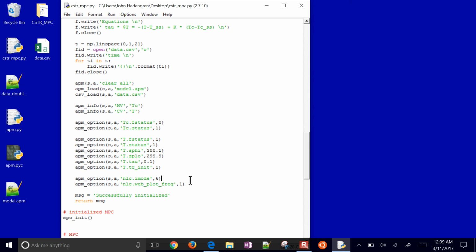I'm going to change this to 0. I'm just going to put a pure deadband there. That's often the easiest one to do. And then in that case, I don't need the tau value, because it's just going to say try to reach that set point high and low as fast as you can.